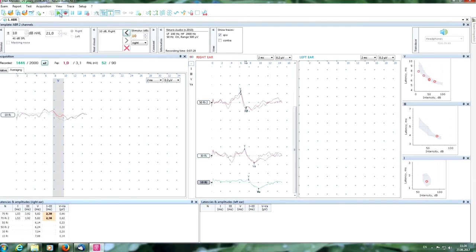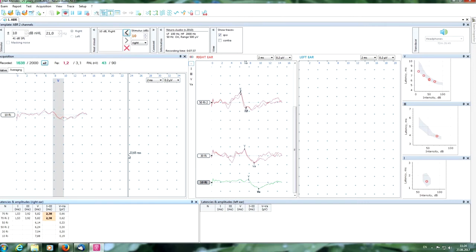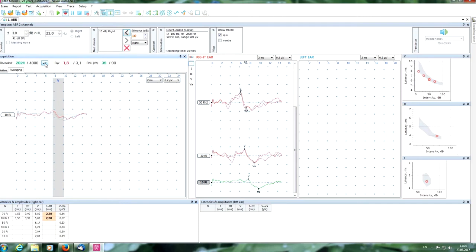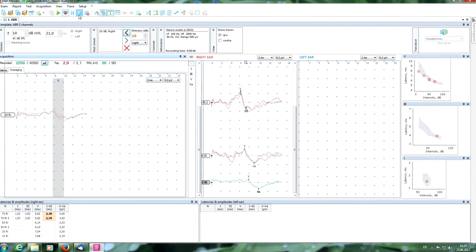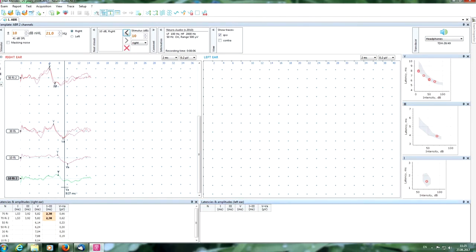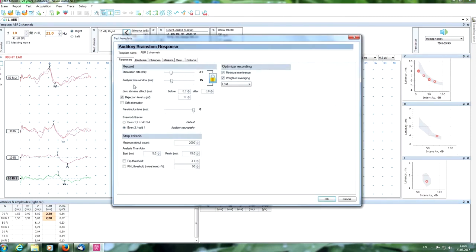Also we get some other curves on the near threshold intensities. When you have any doubt if you get a response or it is just noise, you can increase the quantity of averaging, pushing here for example 4,000 or even 8,000. If you have a good response you can stop. Now we manage the curve inspect and put markers.